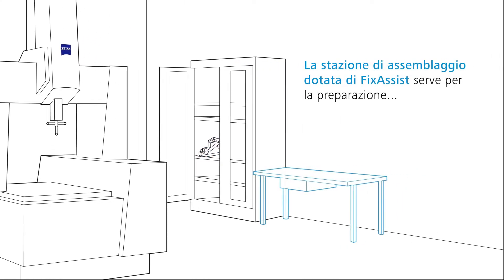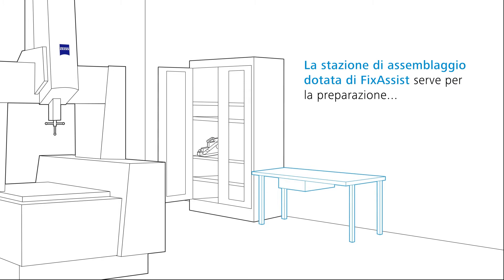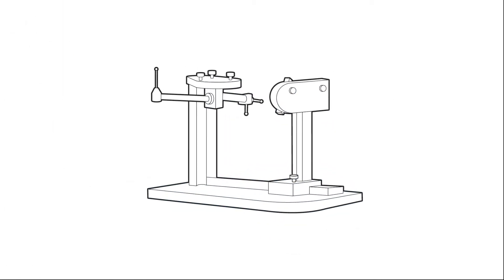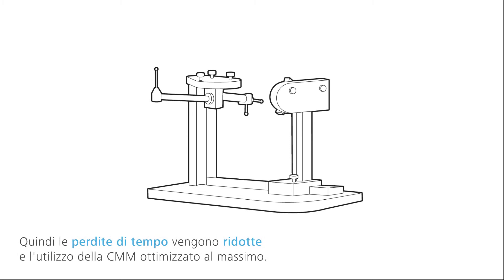The setup station equipped with the FixAssist stylus setup device and the correct tools enable stylus systems to be precisely assembled away from the CMM. Downtimes are thereby reduced and the machine utilization increased.